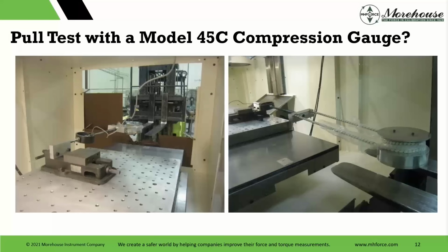Here was an interesting one. The customer called us and they said, we don't understand this. Every time you do the calibration, it's out of tolerance. And our salesperson asked for some pictures. What we found out was that our force gauge, used here in this picture, compression force gauge, model 45C, was being used in a tension application. The threads are not designed to carry the forces in this application, which is unsafe, and the overall setup doesn't look too safe either to bolt something onto a forklift, pull on it. It's what people do, right? Until you know better, it's a problem, right? And then after you know, hopefully you correct it.